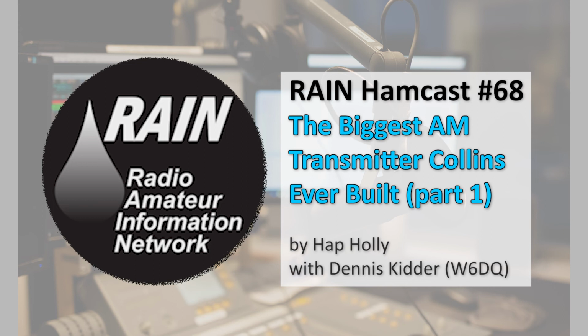What makes this transmitter unique for the time? 250 kilowatt transmitter, meaning if you figure the peak power out is roughly 4 times the carrier power, 250 kilowatts is the carrier power. So this is a megawatt transmitter. They're peaking at 1 megawatt out. This is an auto-tuned transmitter. Why is that important? Well, think about this period of time, 1964.